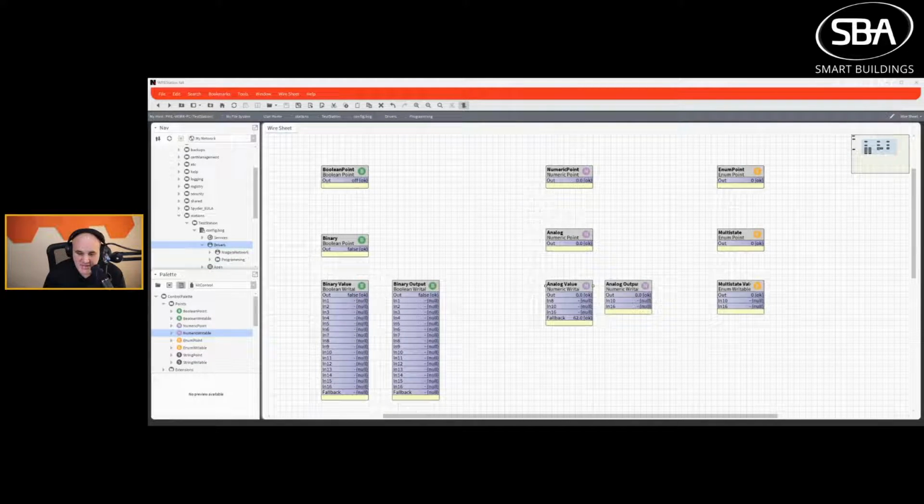So that is the not too terribly complex point objects. I hope that as you leave this episode, you now understand the 3 common object types in building automation. You understand when they would be used. You understand what priority arrays are and why we use them. And you understand why there's priority arrays on values and outputs, but not on inputs.